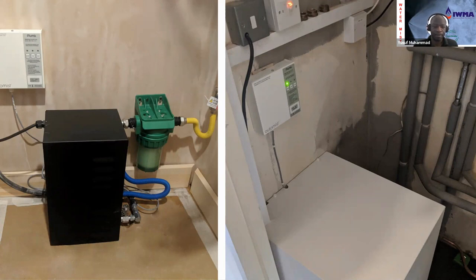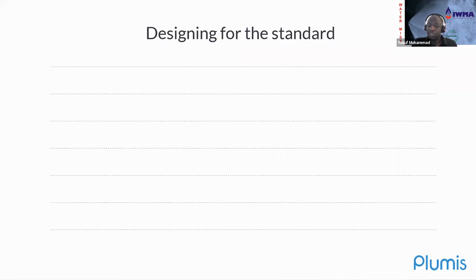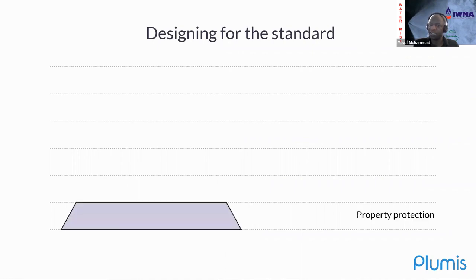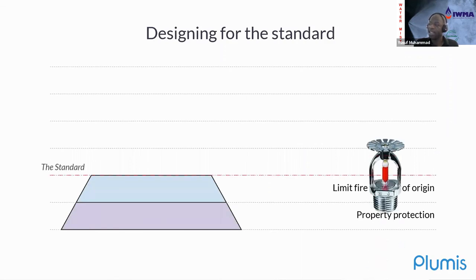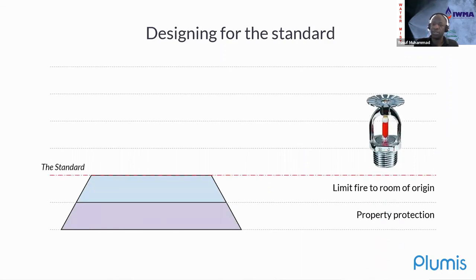So finally, I'd just like to explain what we're trying to do as a manufacturer, and why there's benefit in this approach. We make things slightly difficult for ourselves when it comes to the sales process by doing things differently. Our approach has been to do differently to what most manufacturers do, which is they focus primarily on the standards. So the standards present a really important benchmark, but historically the objective of traditional sprinkler systems was to provide property protection and to limit the fire to the room of origin. So standardized testing is focused around this particular objective.